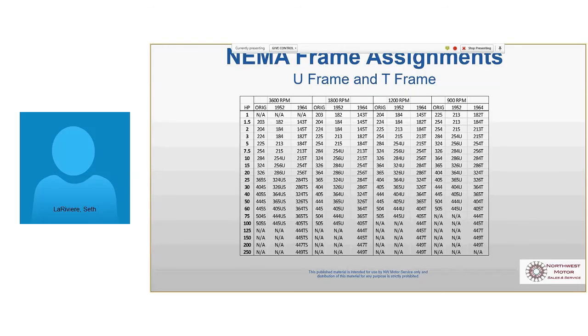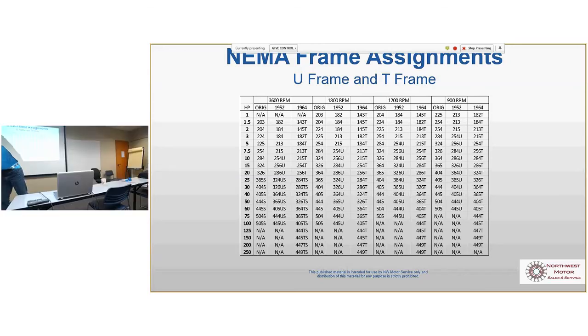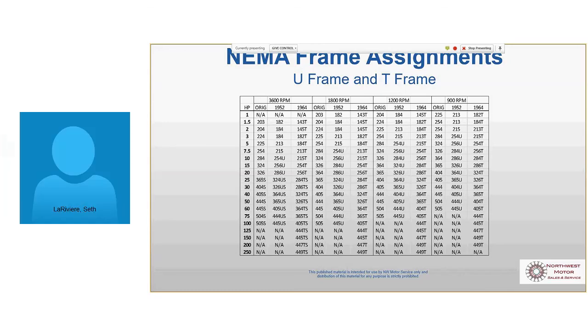So they make transition bases for these, though, that you can take a U frame, put it on a transition base. It brings the shaft height up to the right height for a T frame. The shaft diameters and lengths are the same, so your pulleys are still going to fit. It's mostly what they call the 2F, which is the length on the holes, and the 2E, which is the width on the holes. Those are different. But they make a transition base that makes those adaptions, so you can make that work. There is no transition back from this to this, and this transition from this to this has been obsolete for a long time. But for a while, they made transition bases for those motors, too, from U-frame to original NEMA. But this is where we are today.